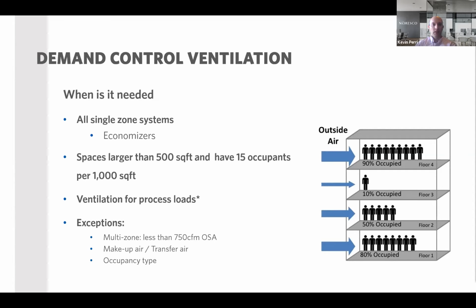And then there are exceptions based on occupancy type. What that means is they put together a list of occupancy types that don't necessarily need demand control ventilation in their eyes. Those space types would be correctional cells, education labs, barbershops, salons, not saloons, salons, sorry, and bowling alley seating areas. So they've added those as exceptions to this section. And then ventilation process loads is an exception. It has an asterisk next to it, but there is an exception based on your process loads.